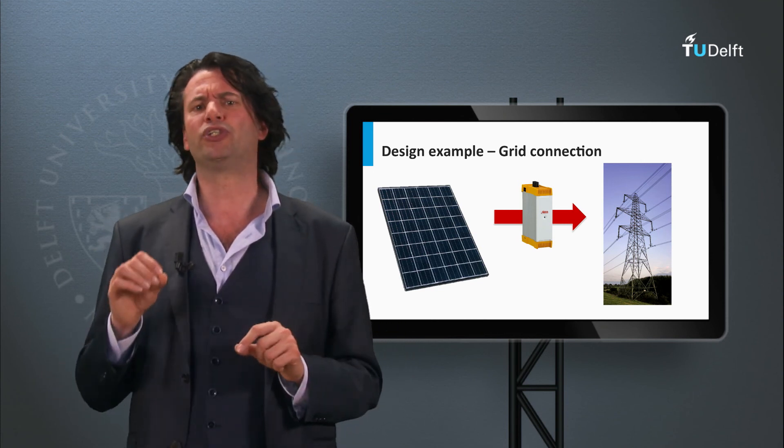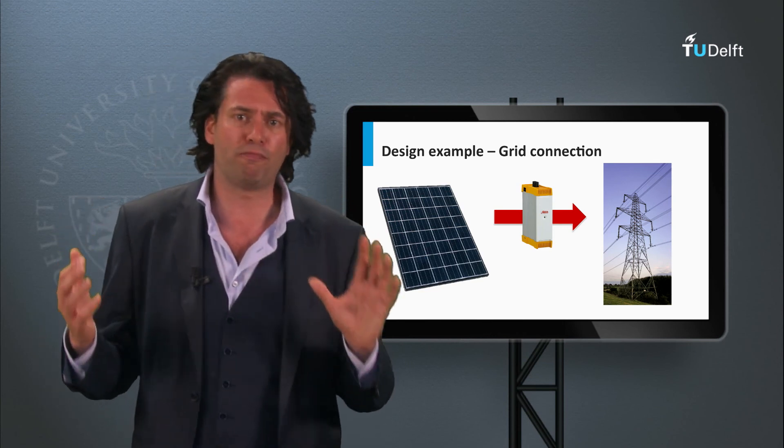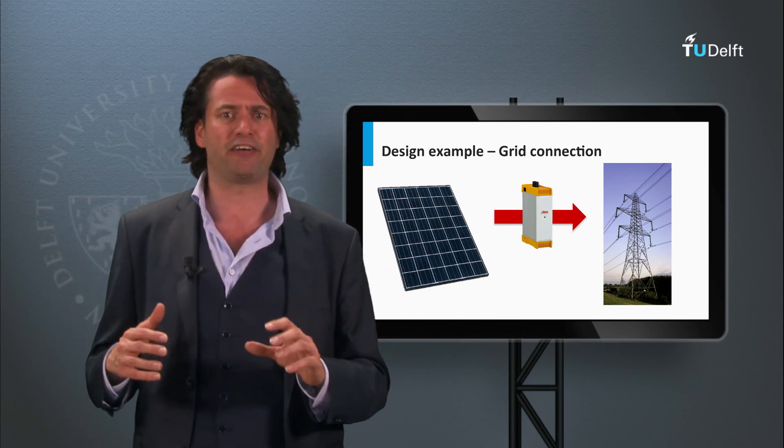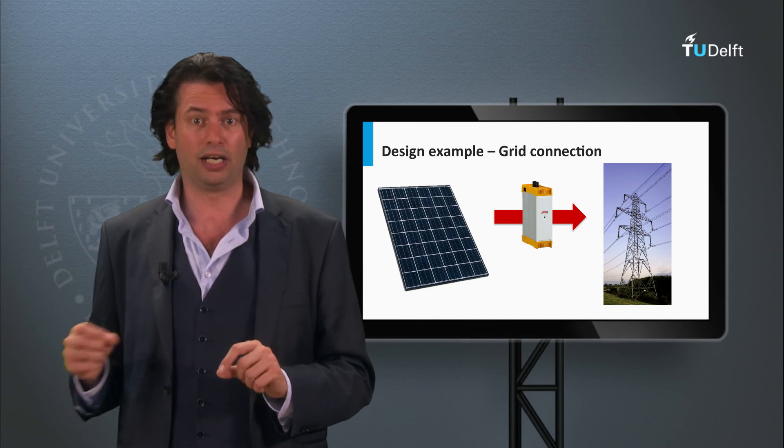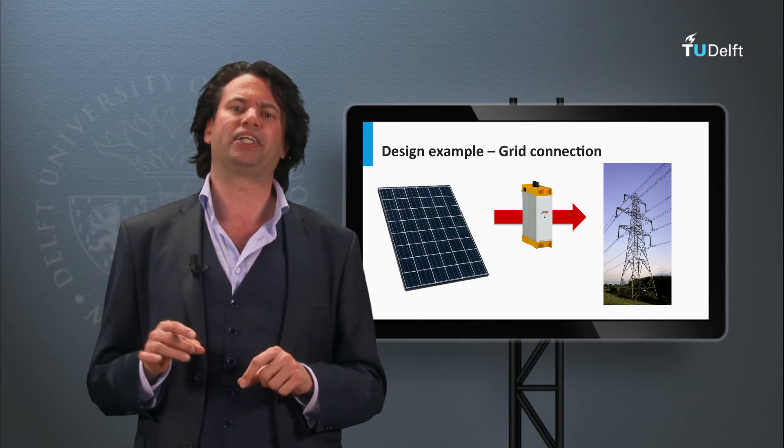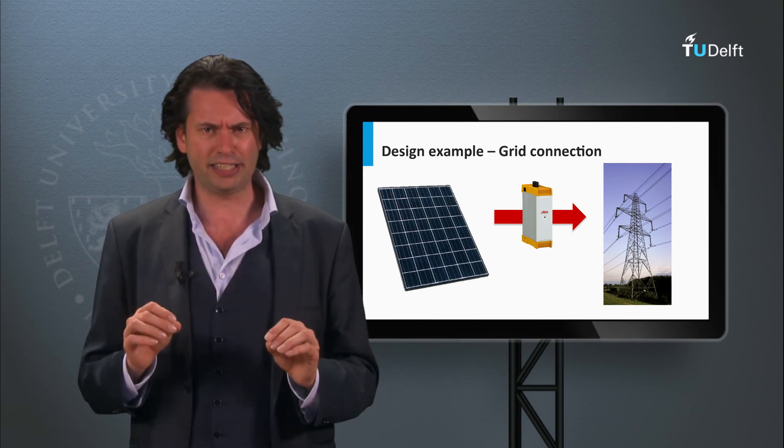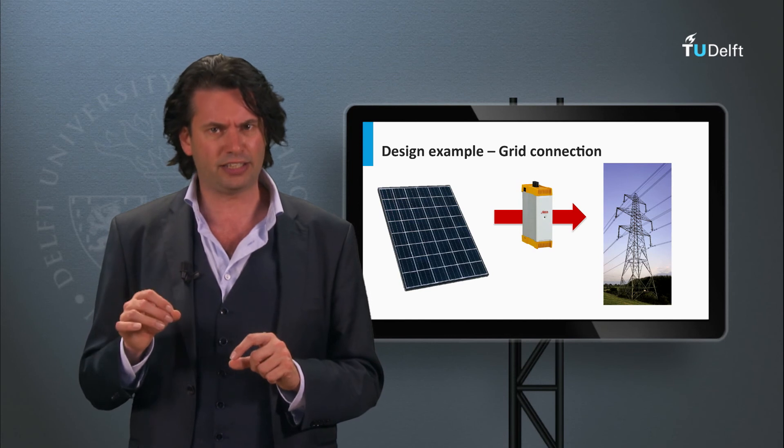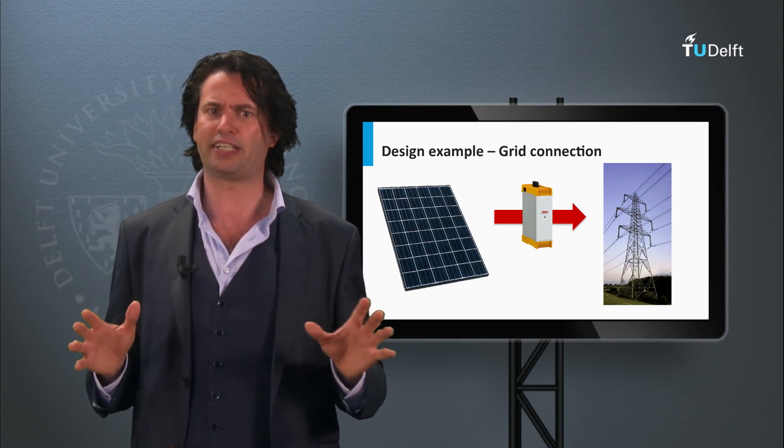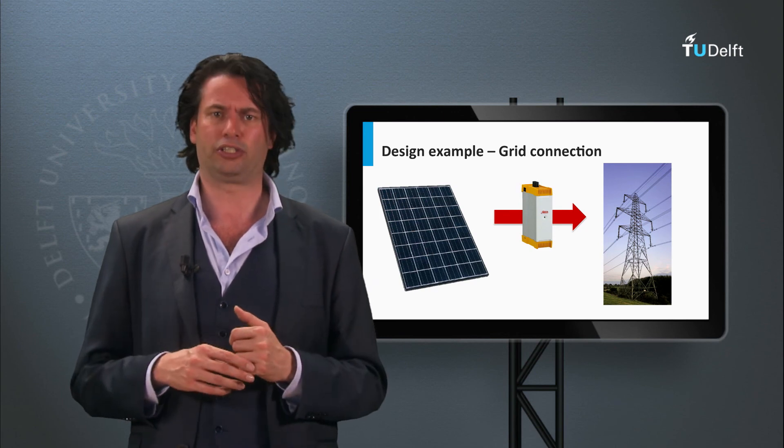This was not true for the stand-alone system, as any surplus or deficit of power had to be met with a variation in the storage size, leading to considerable system costs. Consequently, in grid-connected PV systems it is usually seen that the inverter is sized based on the PV array sizes and not the load size, like in the stand-alone system.